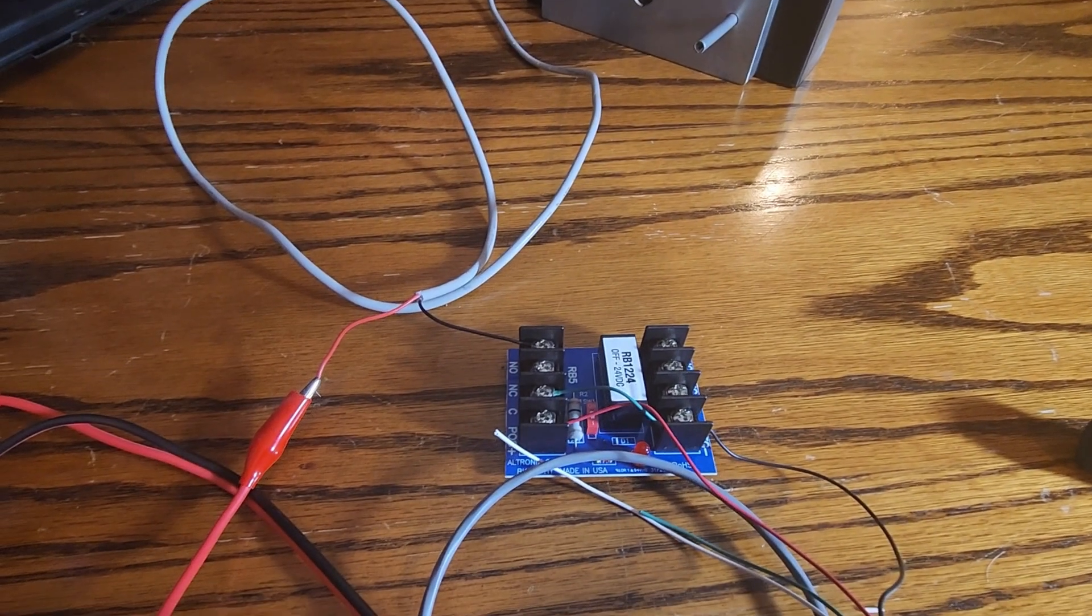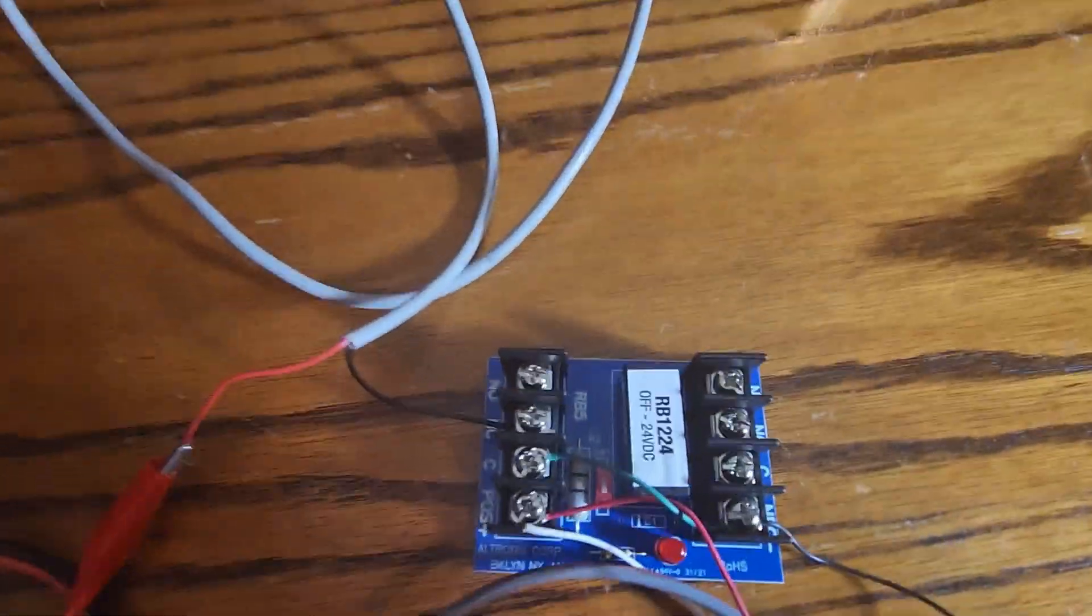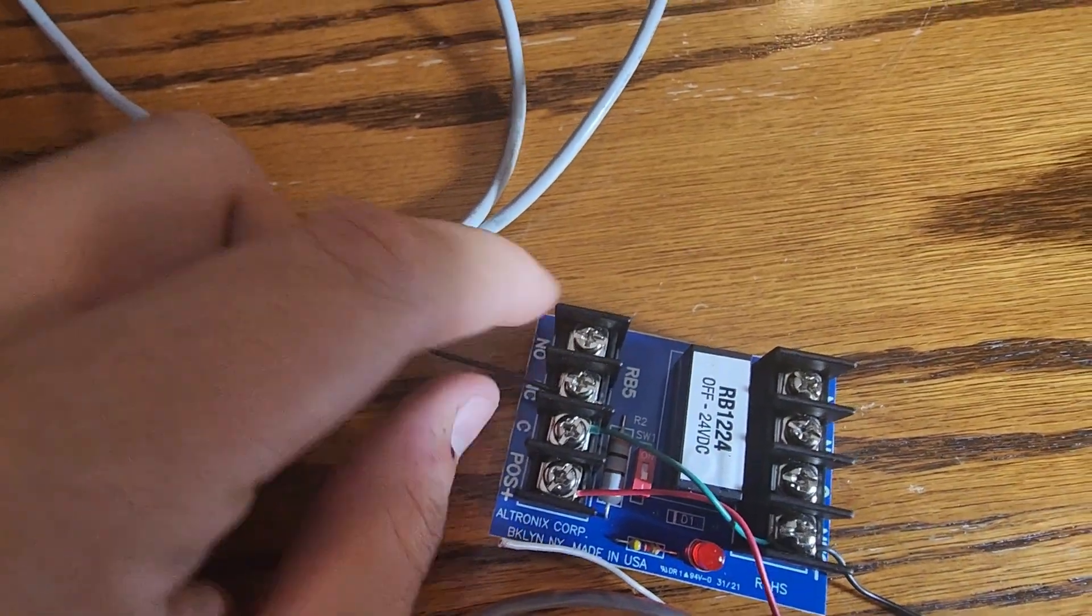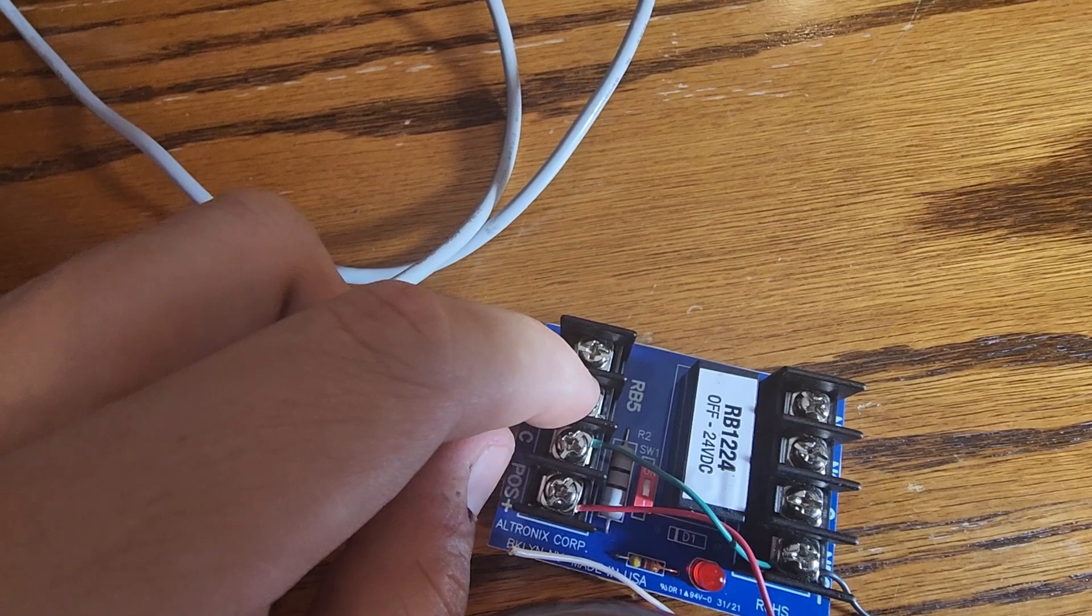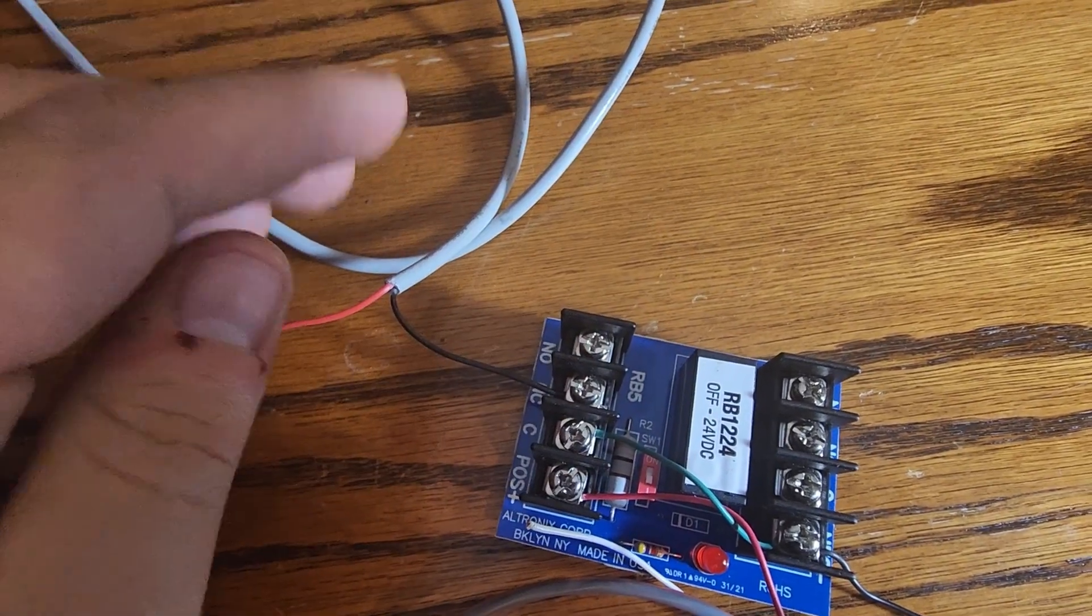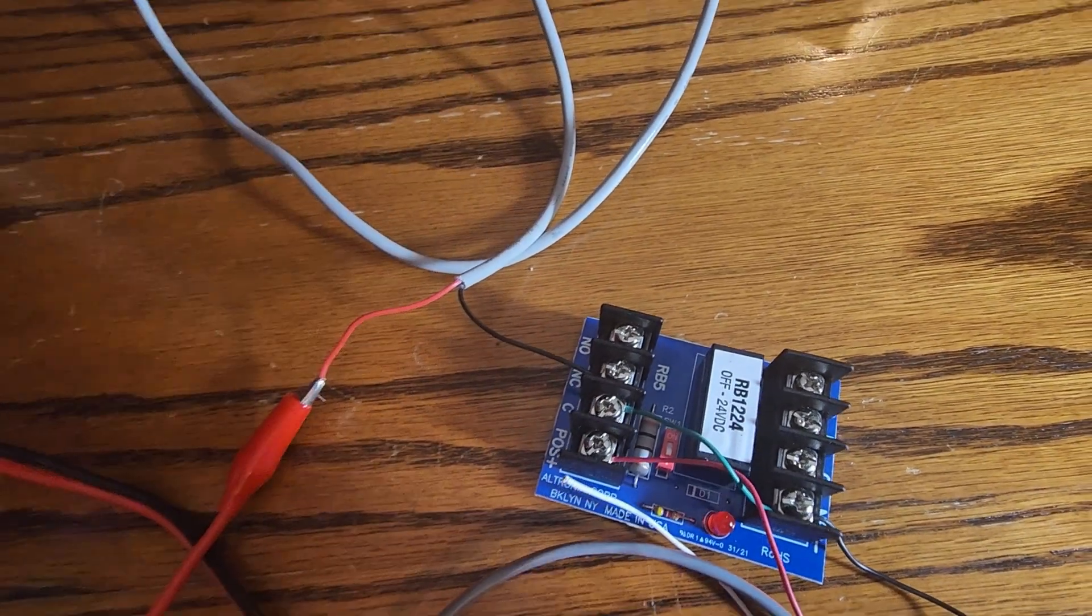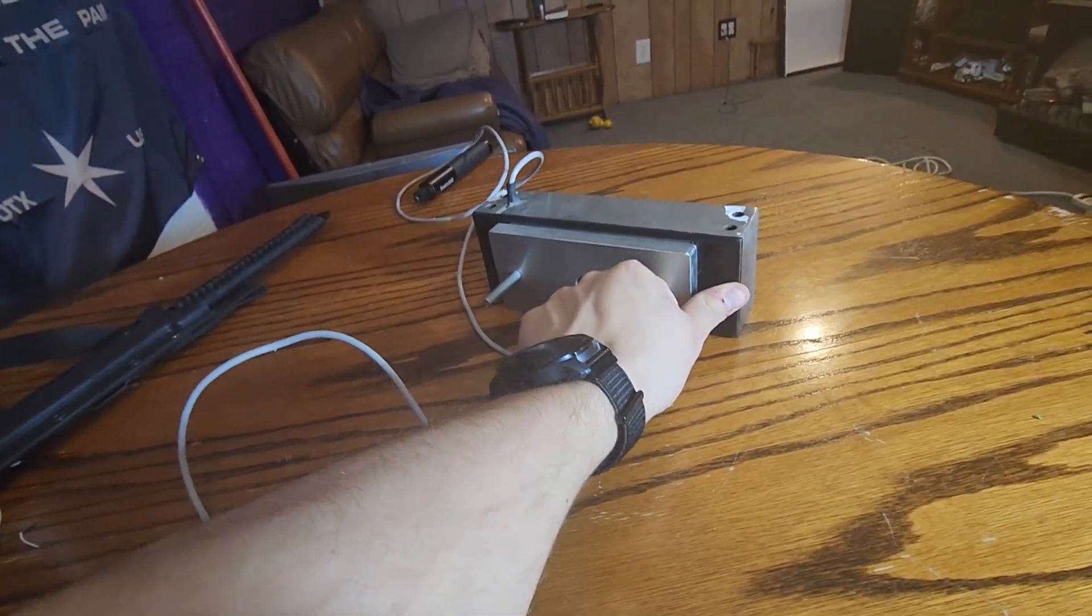What if I wanted this relay to kill a lock? So, as you can see, I have moved the locks negative from normally open to normally closed. This now means that with the relay not engaged, there is current flowing through. You can probably tell because my power supply is humming. And if I go to the lock, I cannot pull the lock apart.